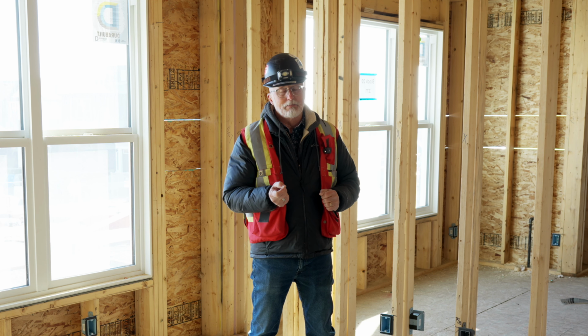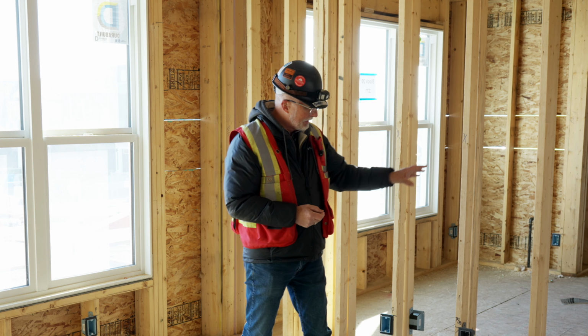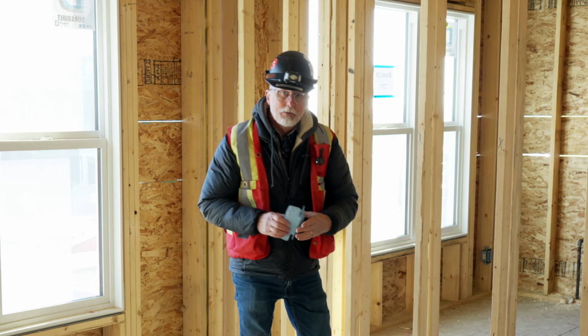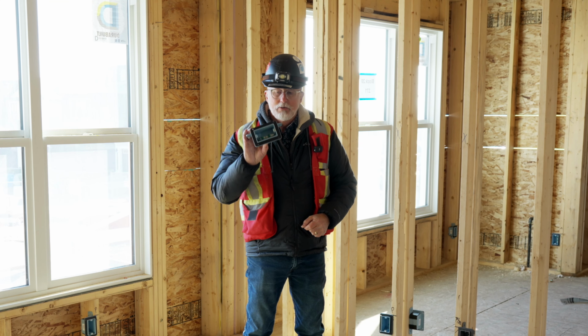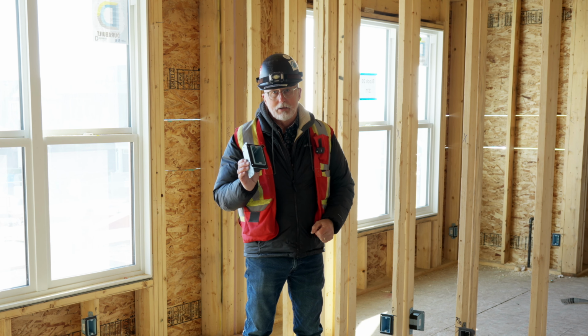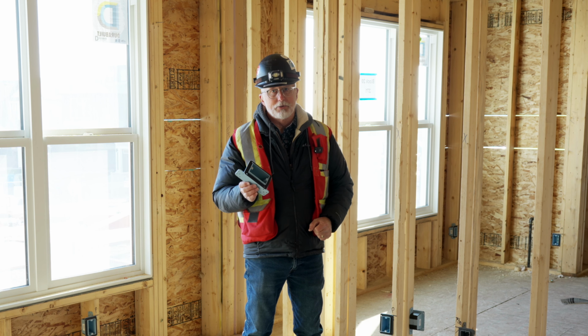Now, with single family, we don't have so much issue with party walls, but with multifamily, we look at things like plugs and switches. If we look at a plug like this, we have an airtight box that has a rubber seal around it. We use those in single family as well. But did you know that this is a special box for a party wall that has a 2-hour rating? So you're using a slightly different box than you would use in a single family house, even though it's an airtight box.